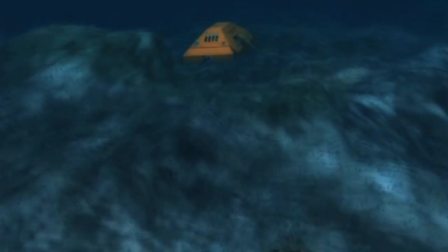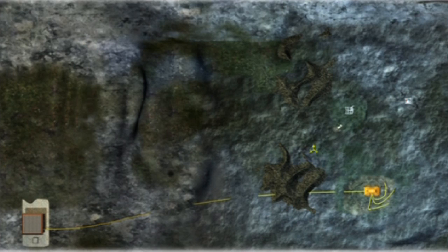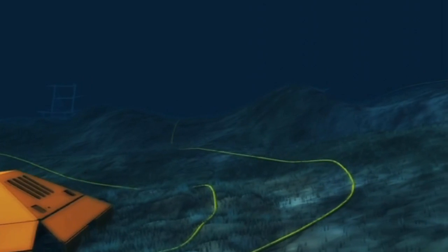It's been years now since that first time that the scientists got together, and they basically gave us the mandate to come out here and start designing things to put into the ocean to be able to serve their science. The VENUS Array consists of a shore station connected to a series of nodes via a powered fiber-optic cable. The nodes serve as a hub for power distribution and provide the communication path between the scientists and their instruments.